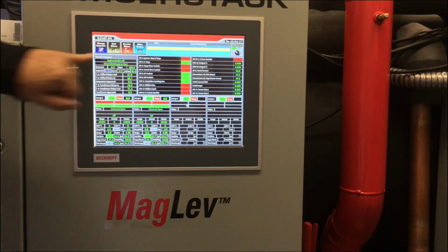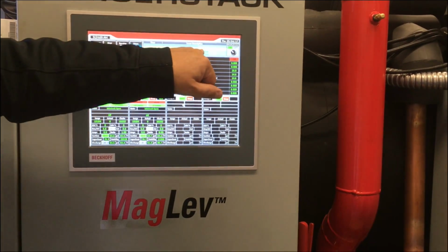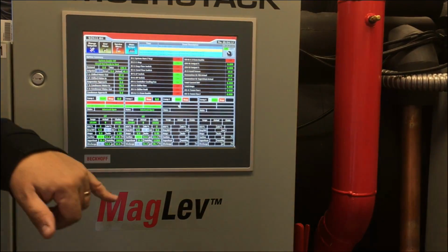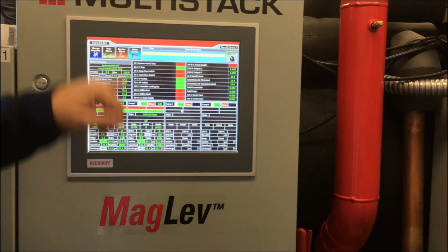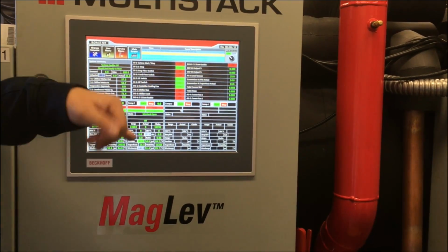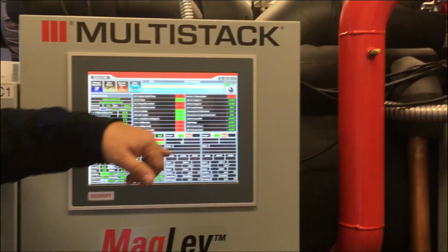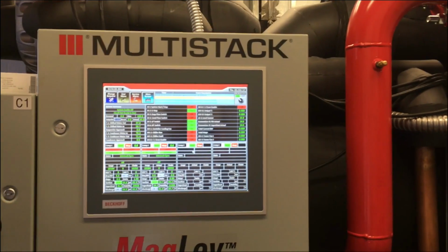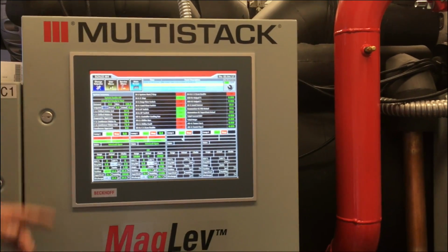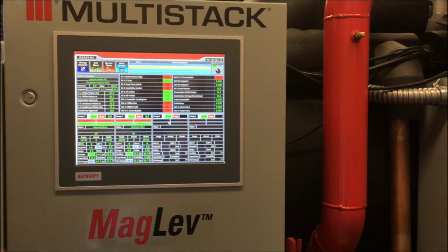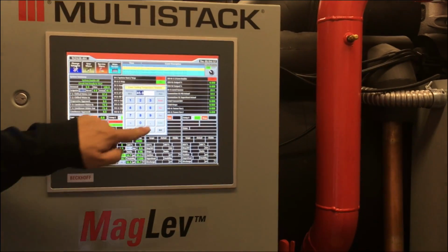Every time you do it, it's going to say operator change cooling temperature set point to 45 or to 42. Or if somebody tried to put in 9, it's going to say operator tried to put in set point 9, did not accept it because 39 is our lowest. Or it may not even record that. It may just not even give you that option. And the highest is 70, I believe. I believe it is, yeah.